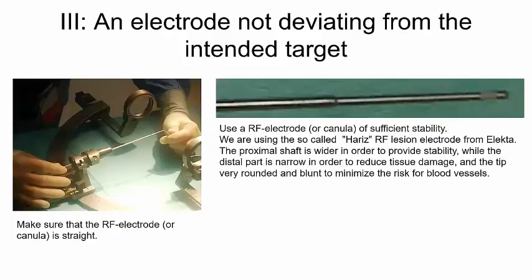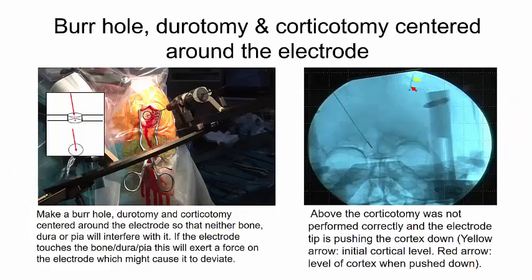We of course need an electrode not deviating from the intended target. We are using radiofrequency electrode to make a channel for the permanent DBS electrode. And we need to have one of sufficient stability. We are using the so-called Hariz radiofrequency lesion electrode from Elekta. The proximal shaft is wider in order to provide stability, while the distal part is narrow in order to reduce tissue damage. And the tip is very rounded and blunt to minimize the risk for blood vessels.